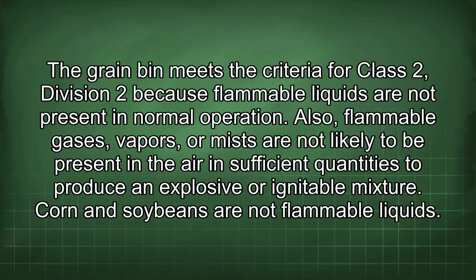The grain bin meets the criteria for Class 2, Division 2 because flammable liquids are not present in normal operation. Also, flammable gases, vapors, or mists are not likely to be present in the air in sufficient quantities to produce an explosive or ignitable mixture. Corn and soybeans are not flammable liquids.